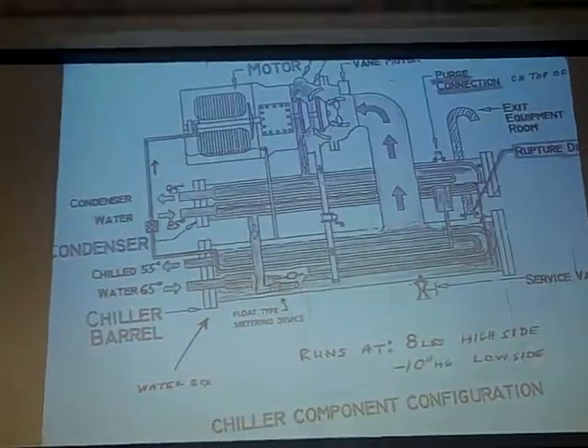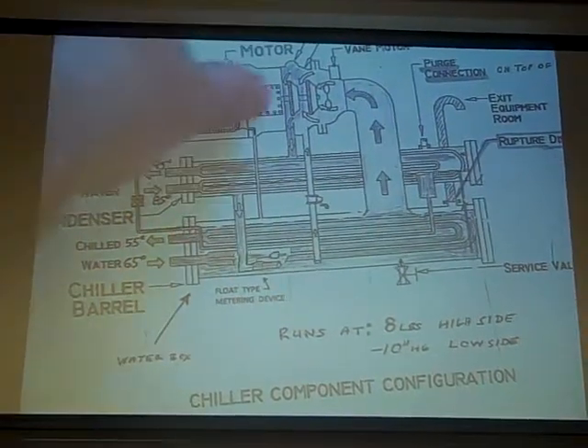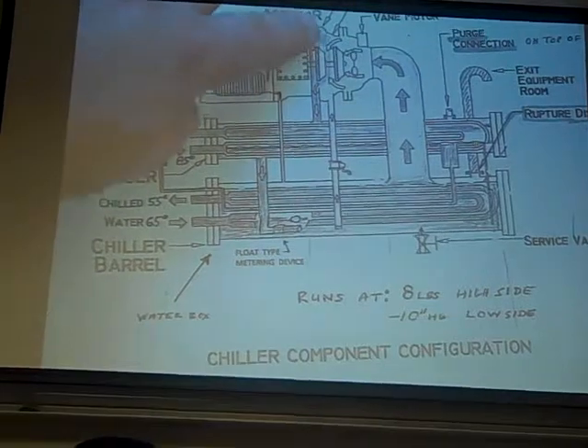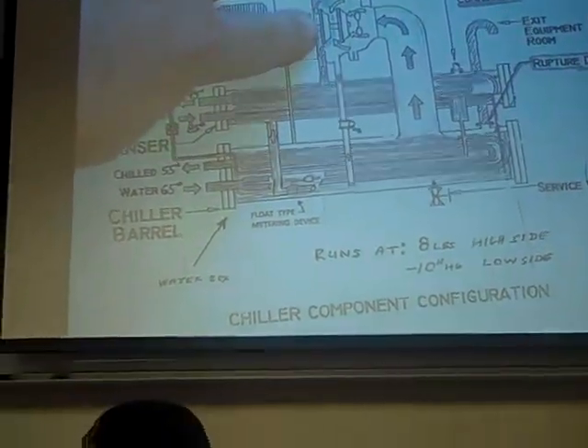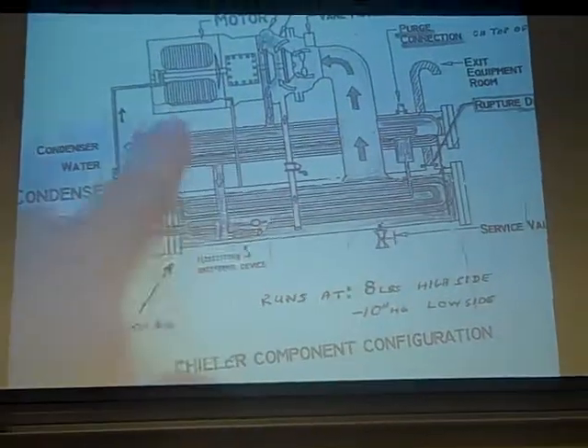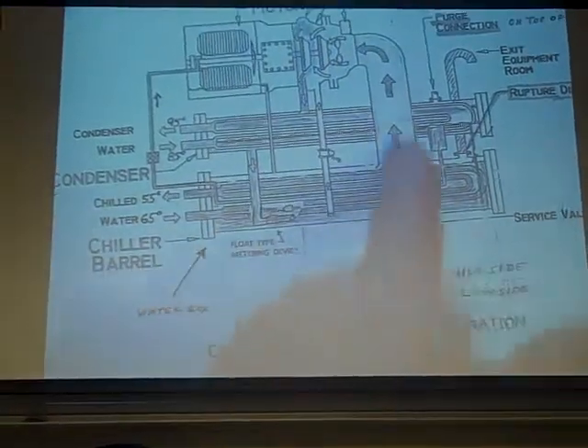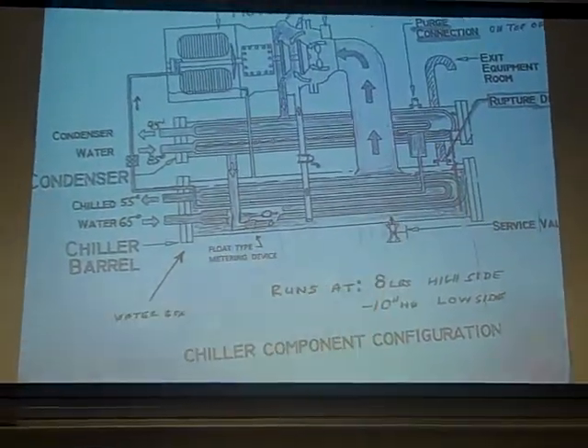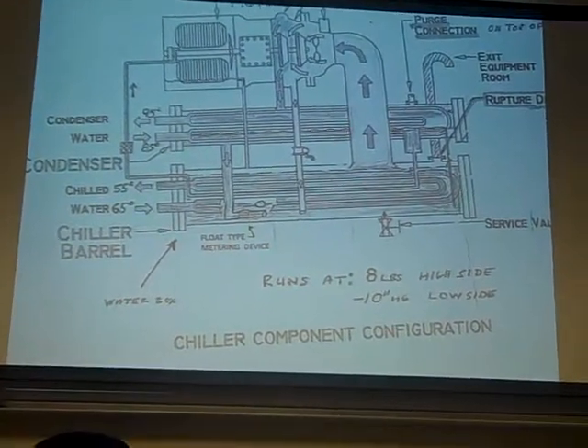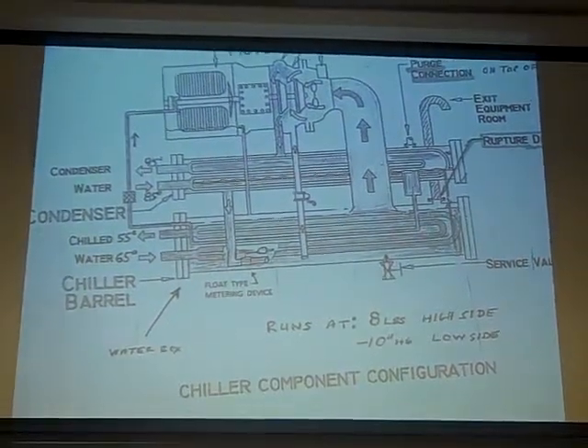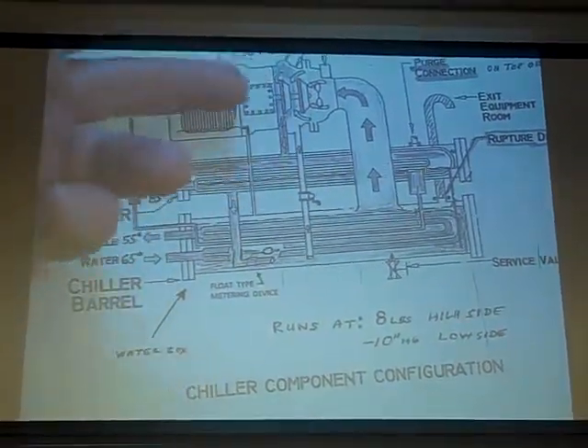So if we flip this over to the next page, kind of a breakdown of a chiller. And you can look on it, you can see back part here is your motor right there. This is your compressor housing. Here's your first stage impeller. Right behind is the second stage impeller. So what that does, it sucks the refrigerant up through here. This is your return or your suction line. On the chiller though, the suction line is about as big around, like an 8 or a 10-inch pipe. It sucks that refrigerant back up through into these impellers based on if it's loaded up or unloaded. One or both of these impellers could be running.